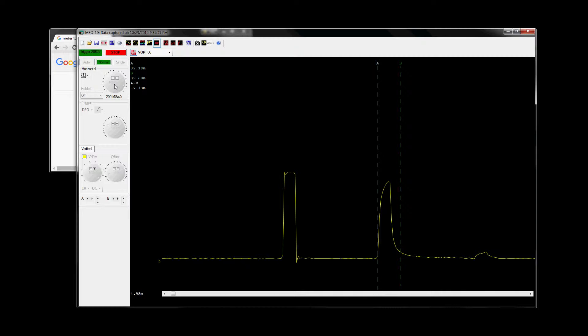TDR stands for Time Domain Reflectometry. It is sometimes called the wire radar. The principle is very similar to conventional radar, where a pulse is sent down the wire. If there is an impedance mismatch, part of the pulse is reflected back. By looking at the shape of the waveform and the time it takes for the waveform to reflect back, we can derive distance and characterize the type of mismatch.